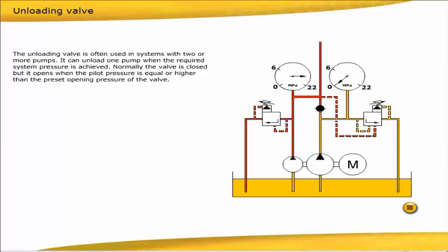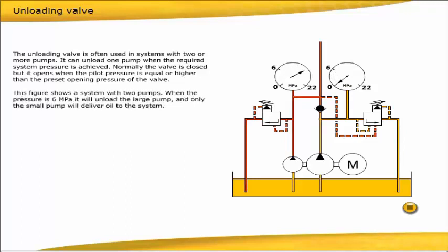Normally the valve is closed, but it opens when the pilot pressure is equal or higher than the preset opening pressure of the valve. This figure shows a system with two pumps. When the pressure is 6 megapascals, it will unload the large pump, and only the small pump will deliver oil to the system. Flow direction is from A to B.